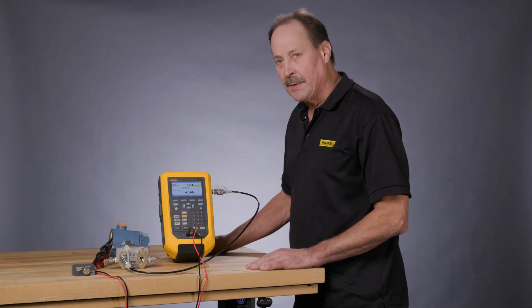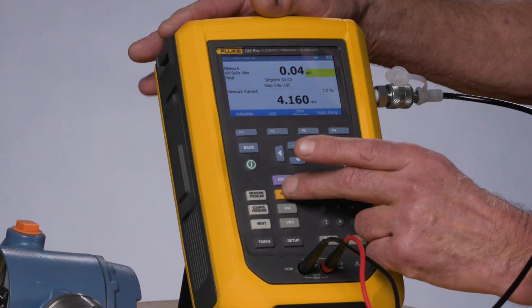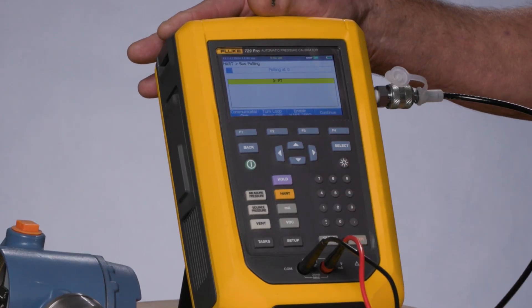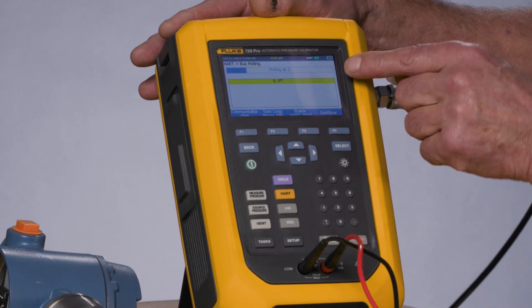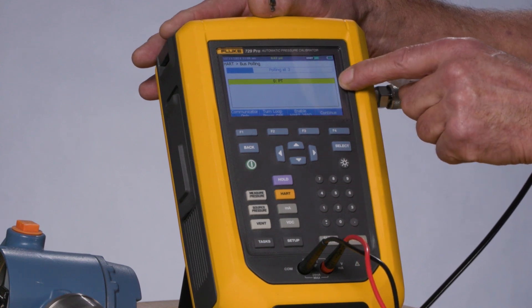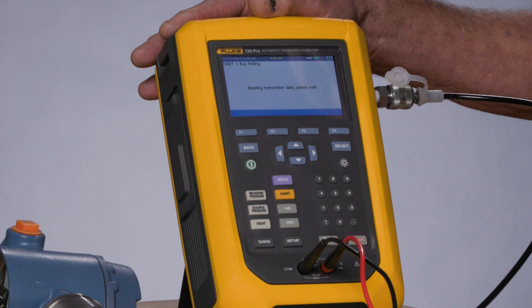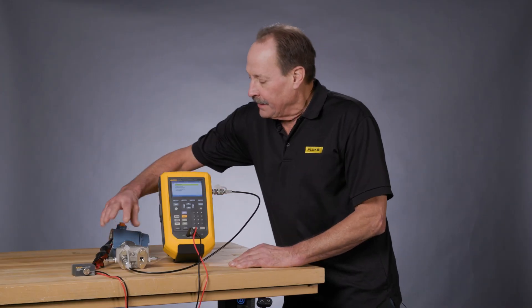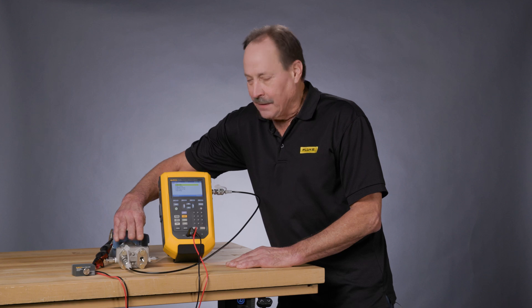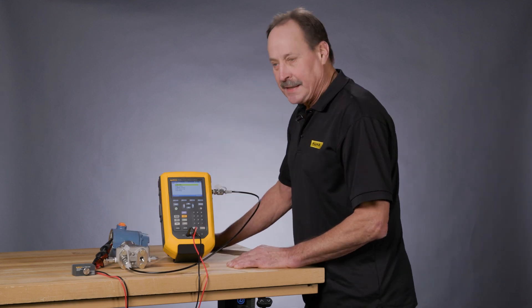To begin the test, we would initiate the test by selecting HART for HART communication. I would turn on loop power and turn on the 250 ohm resistor, and here's the tag number that was found. I press continue, and the calibrator is reading the HART device configuration of this transmitter for our testing.